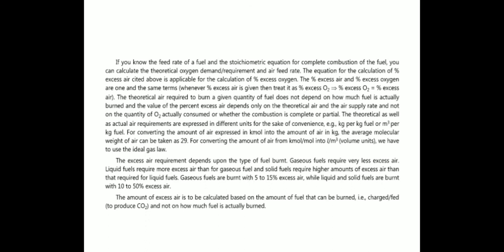If you know the feed rate of fuel and the stoichiometric equation for complete combustion, you can calculate the theoretical oxygen demand or air feed rate. The same equation applies for calculating percent excess oxygen. The excess air requirement depends on the type of fuel: gaseous fuels require very little excess air (5–15%), while liquid and solid fuels require more excess air (10–50%).